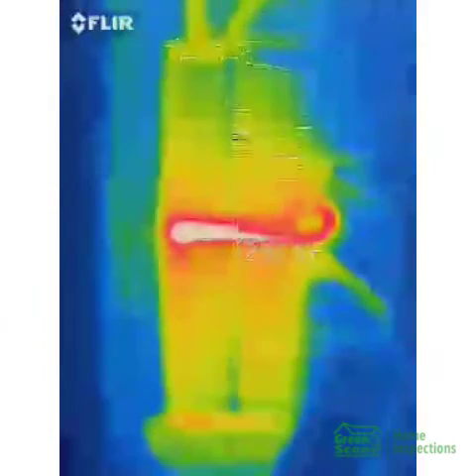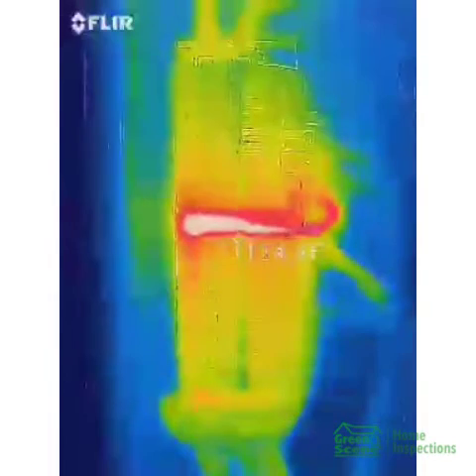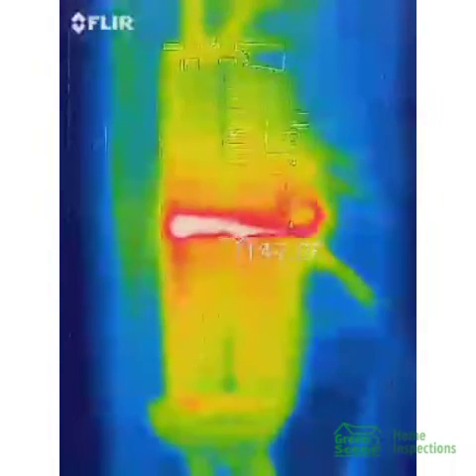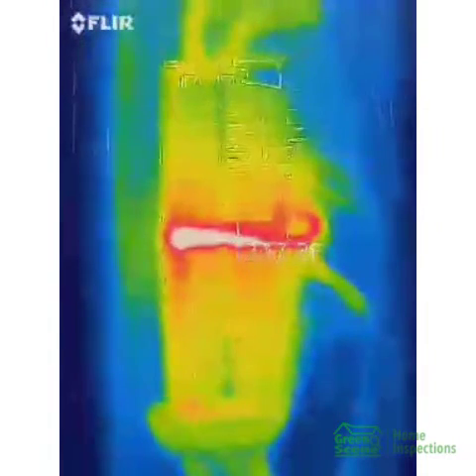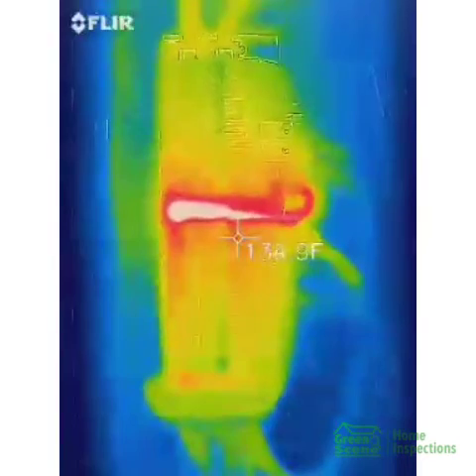I can actually smell it melting and burning the plastic and the conduit, or the sheeting around those wires. This is why we get rid of those Federal Pacific and Zinsco panels. Once again, this is Brian Lindley with Green Scene Home Inspections. Have a great day.